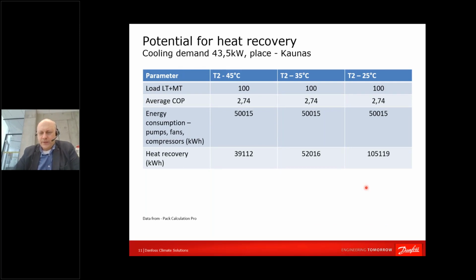Those who would like to manipulate figures and calculate the possibilities of heat reclaim might discover Pack Calculation Pro on the internet and exercise what will happen. Here is an example of a small plant with almost 44 kilowatts of cooling capacity or demand, placed in Kaunas, Lithuania. And we have three scenarios, when the return temperature is 45, 35, 25. We are spending 50,000 kilowatt-hours for fans, pumps, compressors in all scenarios. As regards heat reclaim, with a high temperature we might reclaim 39,000. With 35, it's 52,000. And with 25 degrees, we can get 105,000 kilowatt-hours of energy back.